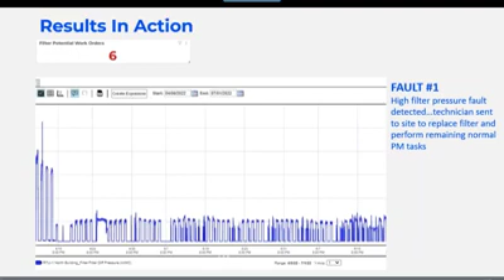Normally on the scheduled PM contract, this unit was getting serviced on a quarterly basis. Now having the data to back that up, it turns out that this filter didn't need to be replaced that often, right? It turns out it was more like 6, 7, 8 months that the filter was good. What that allows for is doing service more on an as-needed approach, and it allows service companies to be more effective and efficient with their time. We want our best technicians taking care of the issues that matter instead of potentially going out and doing all this service on scheduled PM visits that might not actually be needed. So this type of condition-based maintenance approach allows for more efficiency and more productivity out of service contracts.